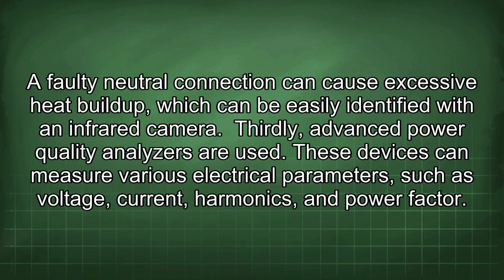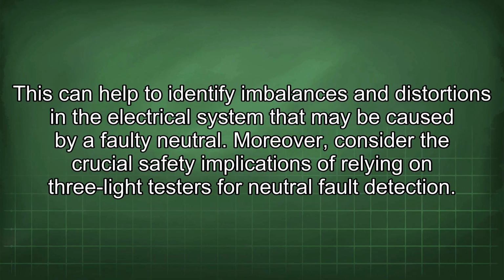Thirdly, advanced power quality analyzers are used. These devices can measure various electrical parameters such as voltage, current, harmonics, and power factor. This can help to identify imbalances and distortions in the electrical system that may be caused by a faulty neutral. Moreover, consider the crucial safety implications of relying on 3-light testers for neutral fault detection.